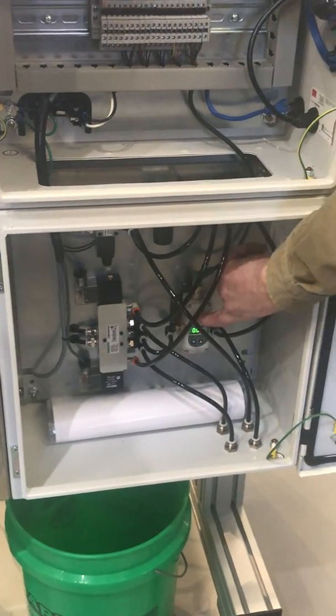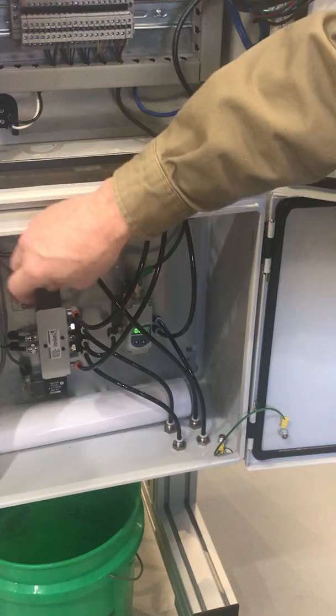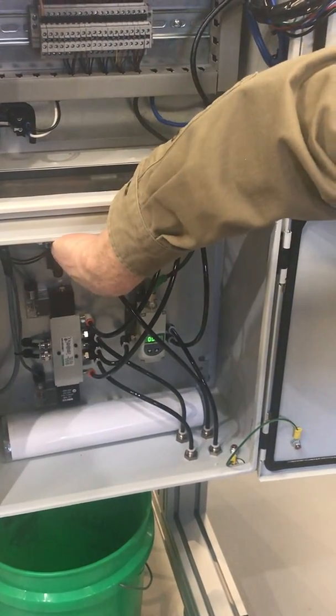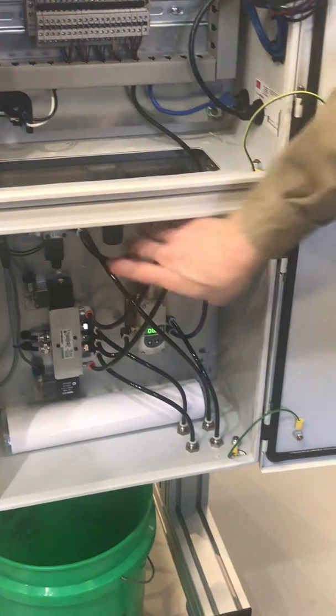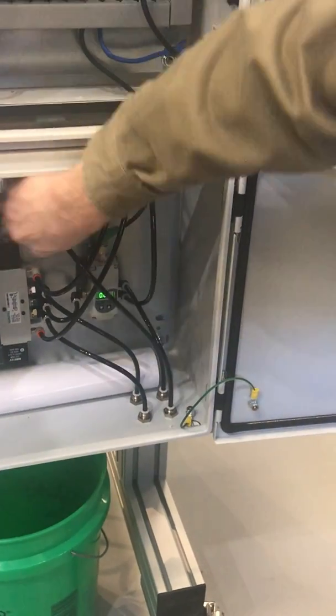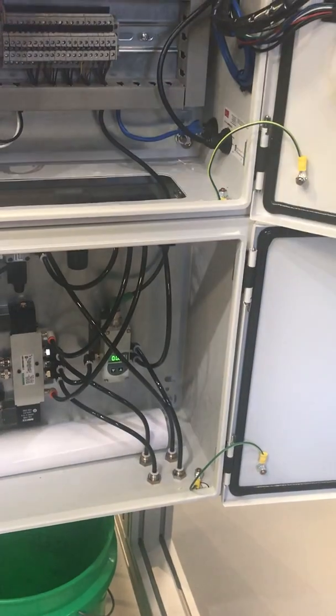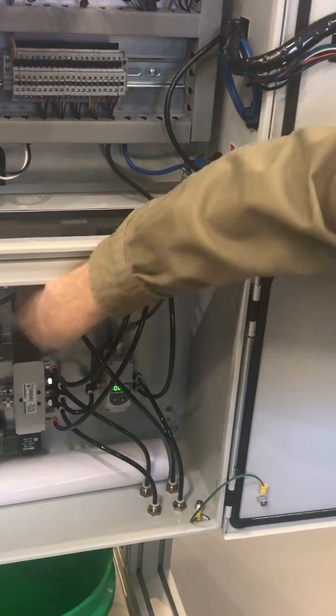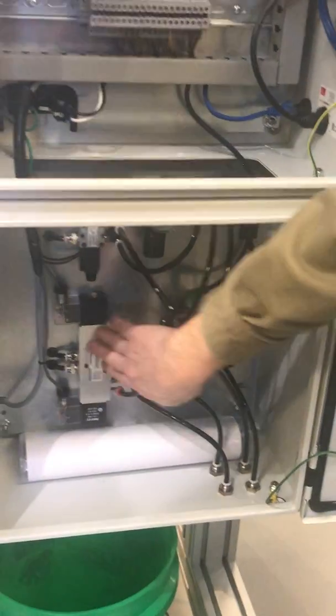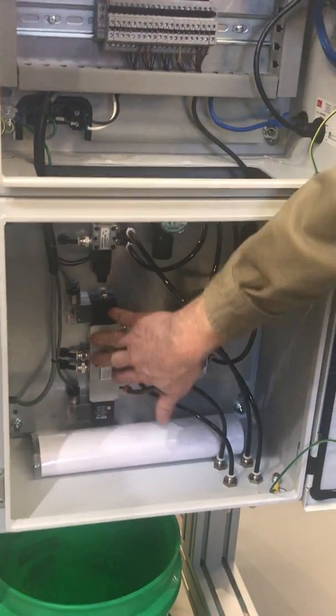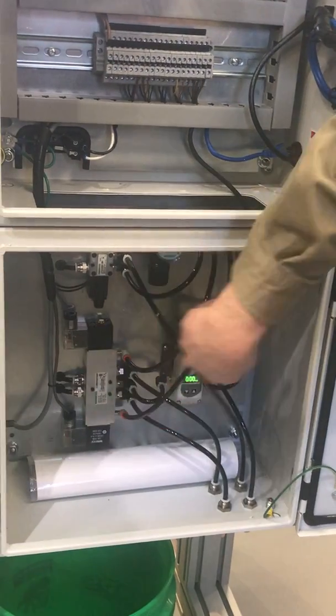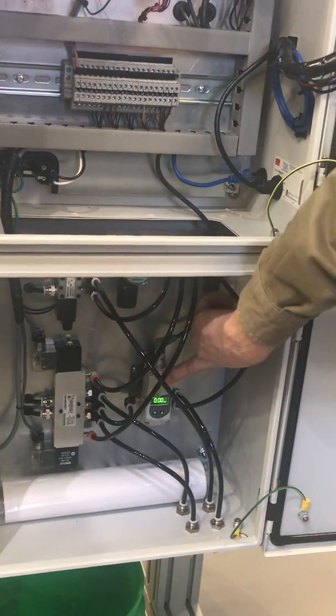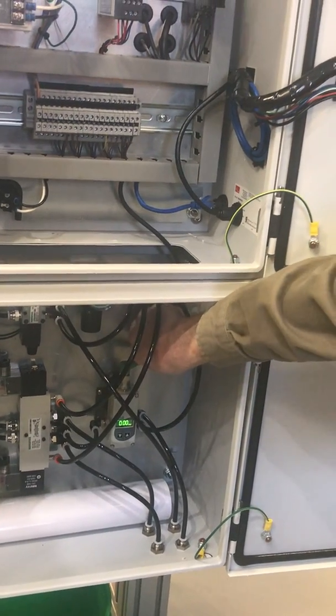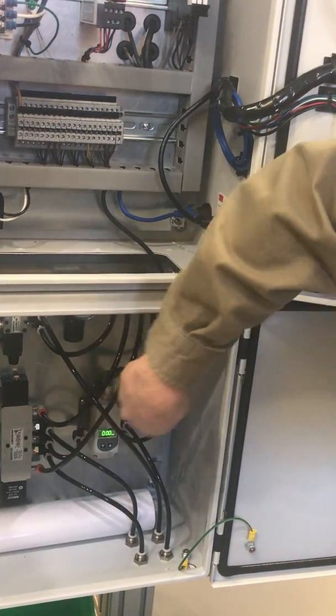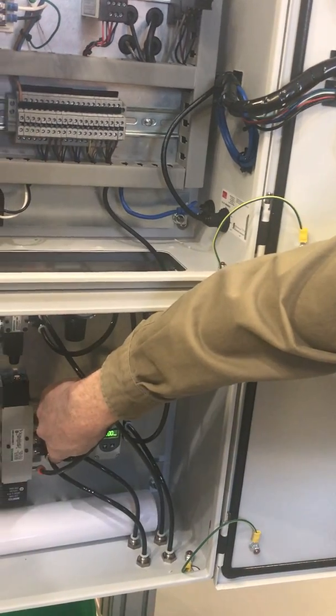So then down here, this is sort of the pneumatic stuff, and this is the interesting thing. Your air comes in and goes to a regulator. We have it set right now at 80 pounds, and so you've got 4 80-pound lines. One goes to this valve. That valve opens and closes that ball valve back there. So your outlet valve on and off. And then this one is extend, retract for your main water ram. But it's fed this pressure. And this is the thing that takes a signal, an analog voltage in, and converts the line pressure to variable pressure. So this is a really cool thing.